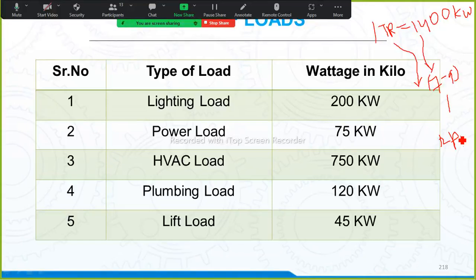But after that, once the compressor switches on, after 30-40 seconds, whatever full load current it has to take, that is 7 to 9 amps, it will take only that much current. But at the time of starting, it takes high power. Yes or no?